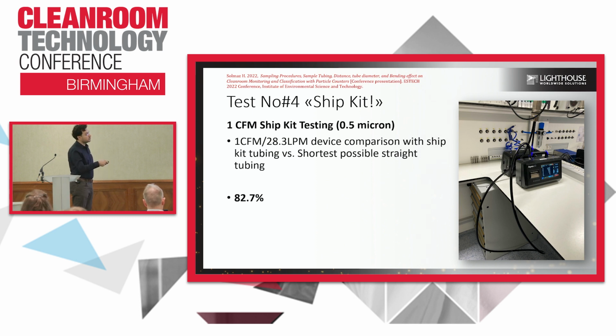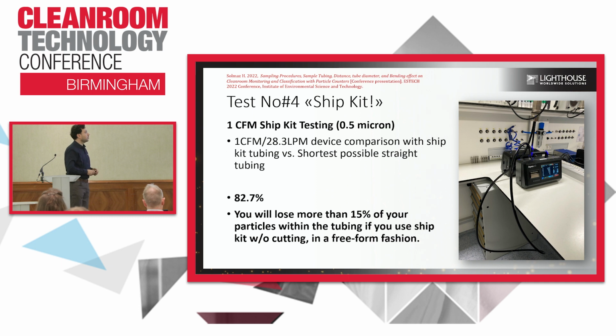So we introduce it to one particle counter as a test, another is the unit under test and the reference. So the difference between these two, 82.7, which means more than 15% of particles are being lost within the tubing.